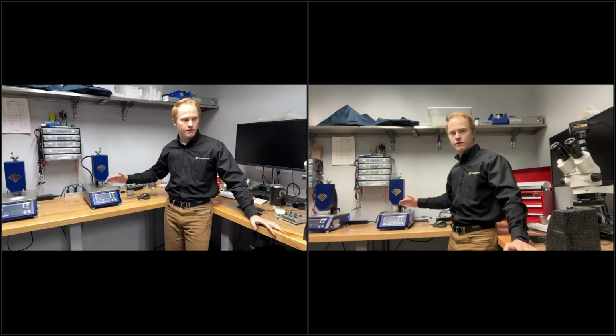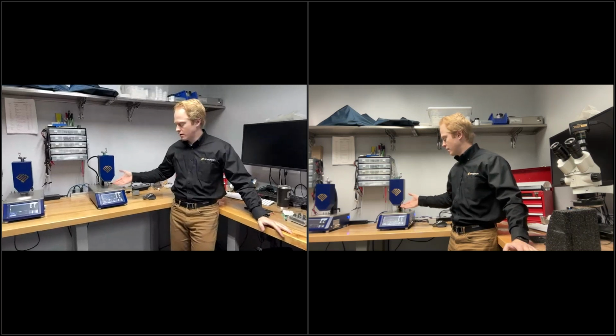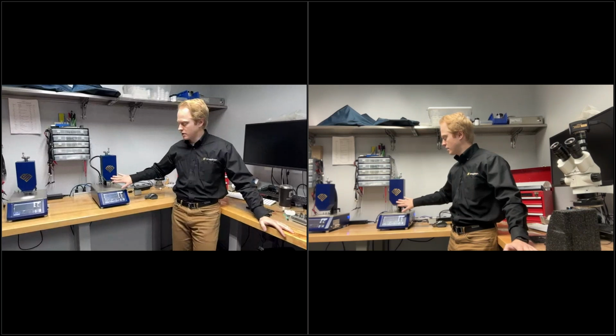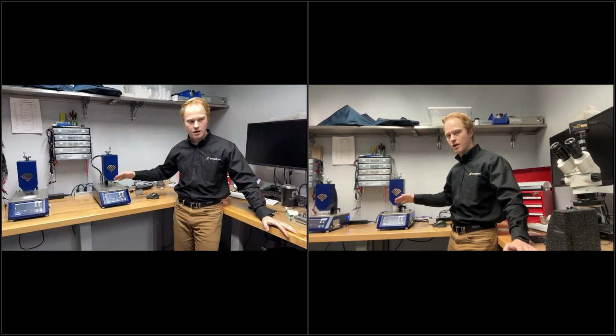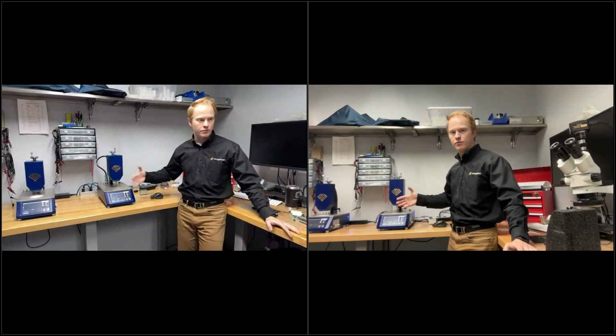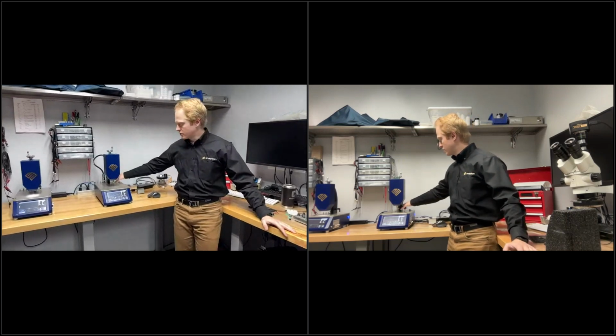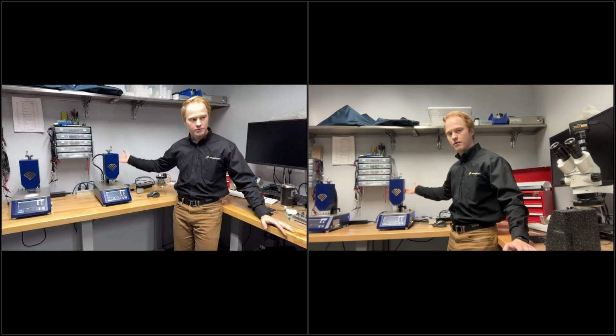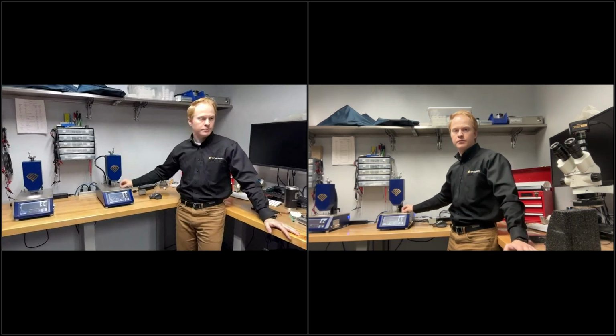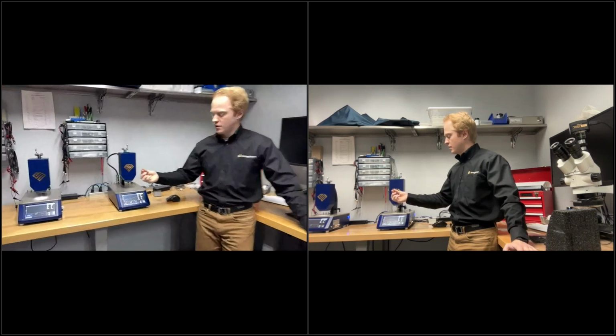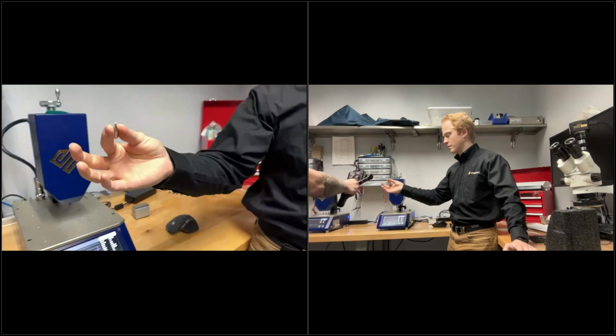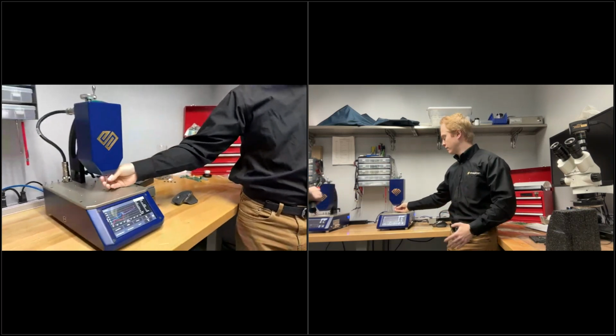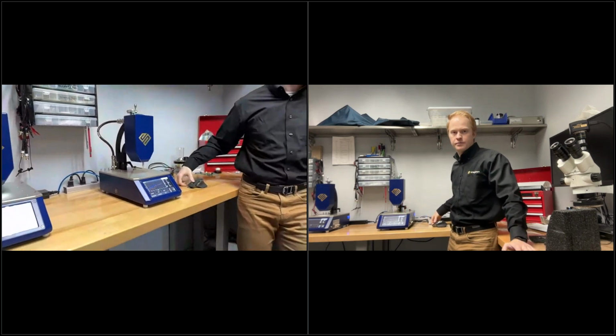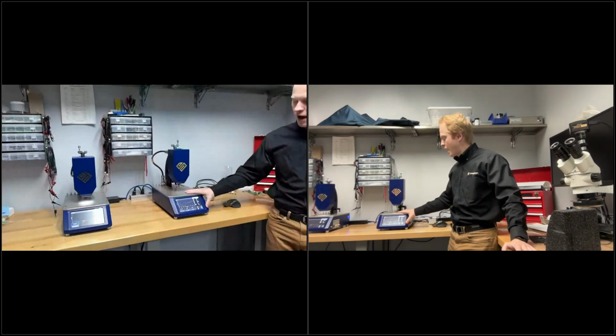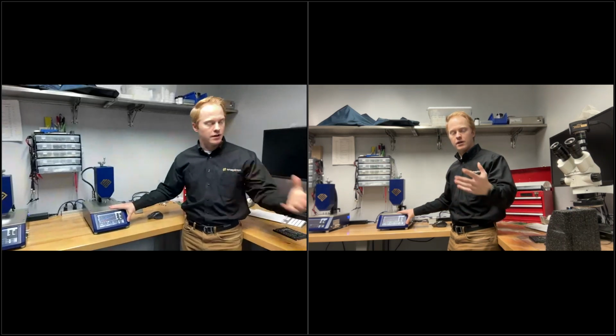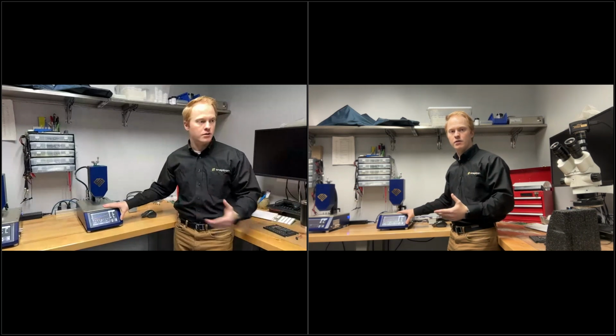Other options, such as customization for this machine - there are quite a few different ways you can spec this machine out that we offer. The standard load cell has a capacity of 5 pounds currently. We can go all the way up to 20 pounds for those high spring rate applications. We also offer neck extensions that will move the entire force measurement head up an extra 3 inches or so. And then we also offer multiple actuation tips - the standard one is a 50 thousandths test tip. We also offer a kit with various different sizes so it'll match your application perfectly. Other than that, we can also offer custom software packages to go along with the Sapphire that will fit exactly your use case and operational workflow. It just depends on what you need - we are very flexible.